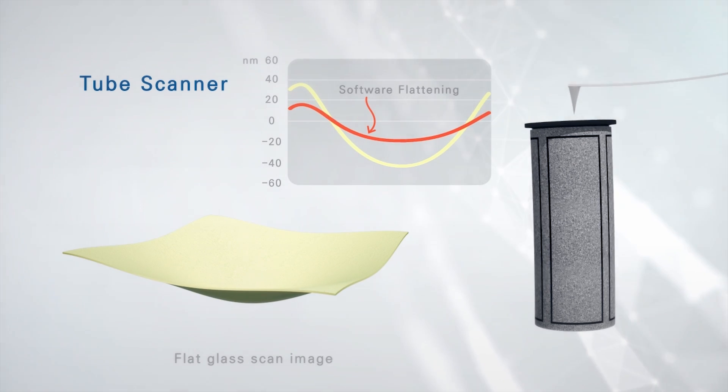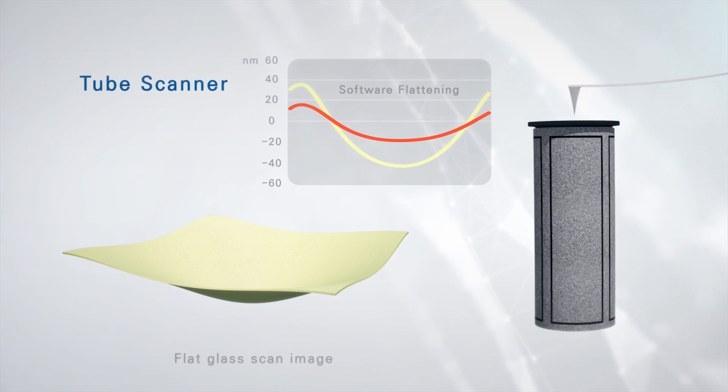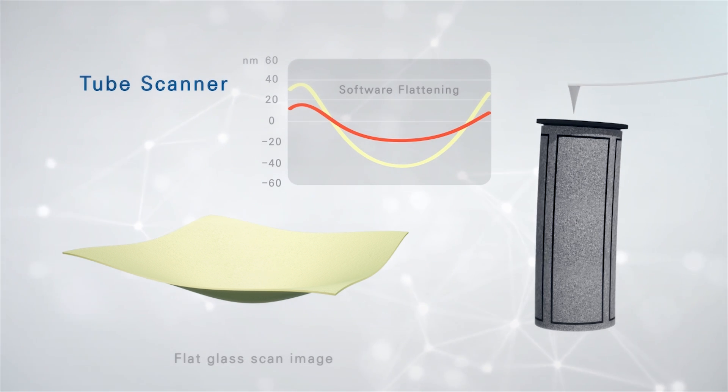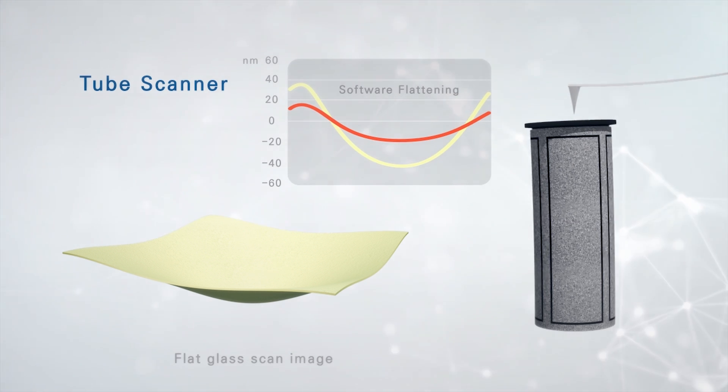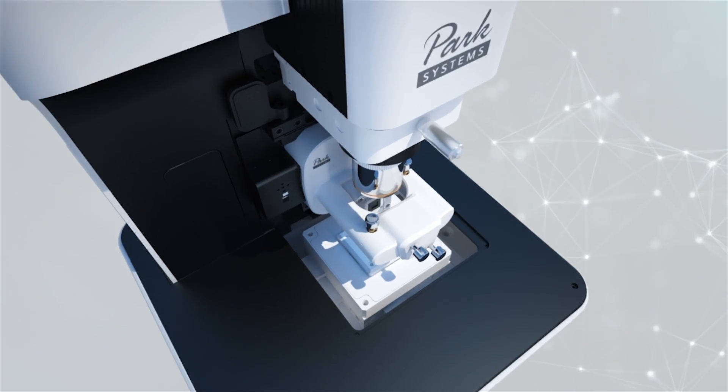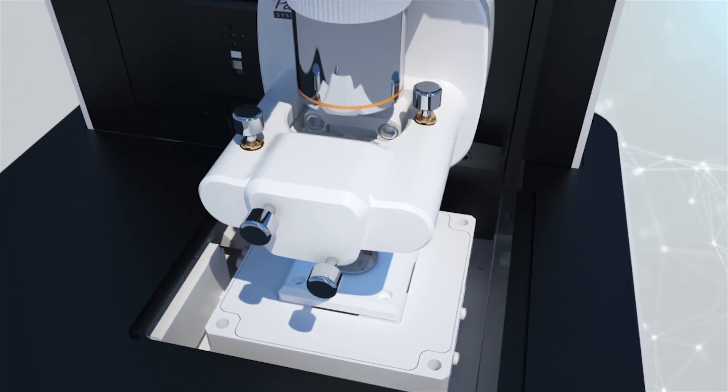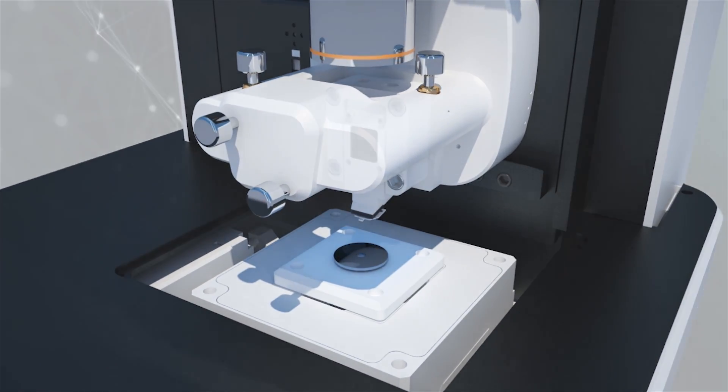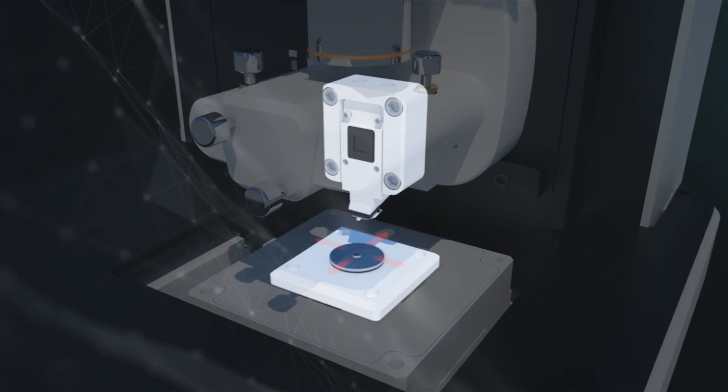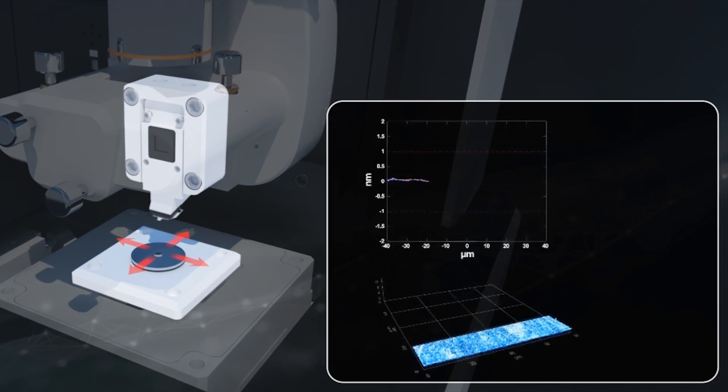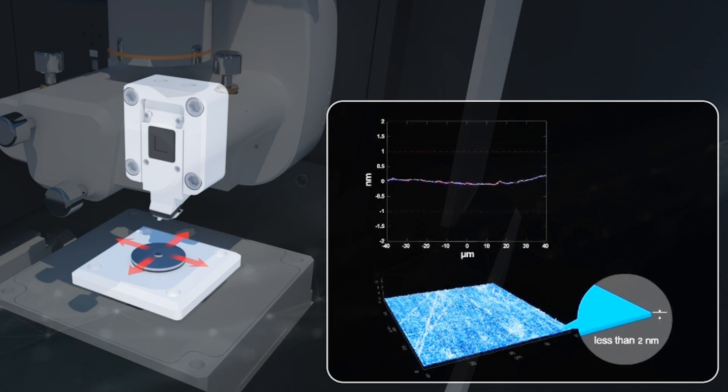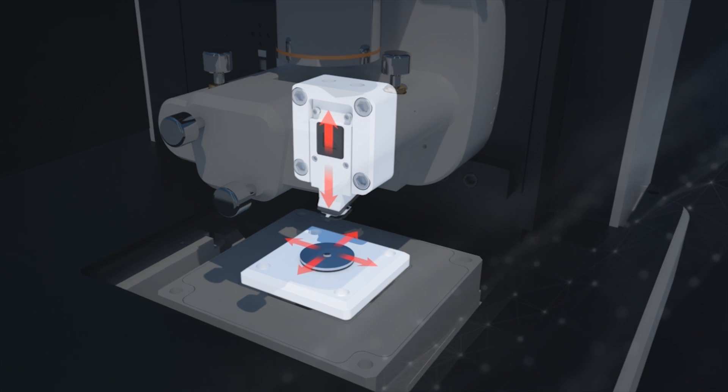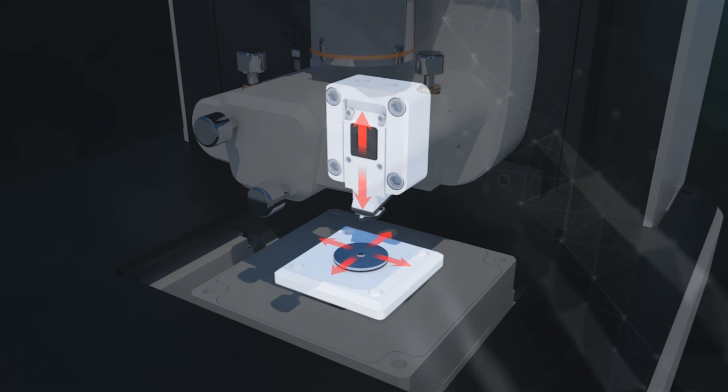In contrast, the decoupled scanner design developed by Park Systems consists of flexure-based independent XY and Z scanners so that measured images can be free of distortion and excellent in linearity and orthogonality regardless of scanning range or sample size and at any scan location or speed.